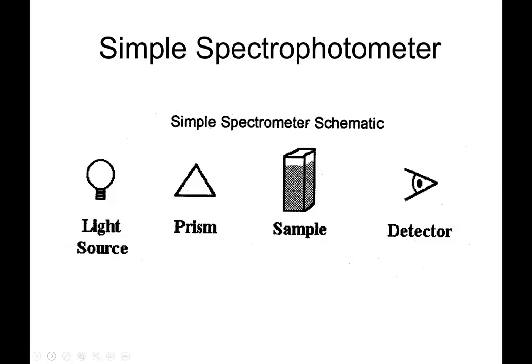Here's how we make one. We take a light source—and all light sources, unless it's a laser, are going to have a broad variety of wavelengths. You pass that through a prism, which separates out the various wavelengths of light. You could also use a grating instead of a prism. The easiest place to see a grating is if you have a CD—if you hold it up to the light and move it back and forth, you'll see the rainbow colors. We need something to separate the light into individual wavelengths, then pass it through the sample, and then we've got a detector to measure how much light made it through.